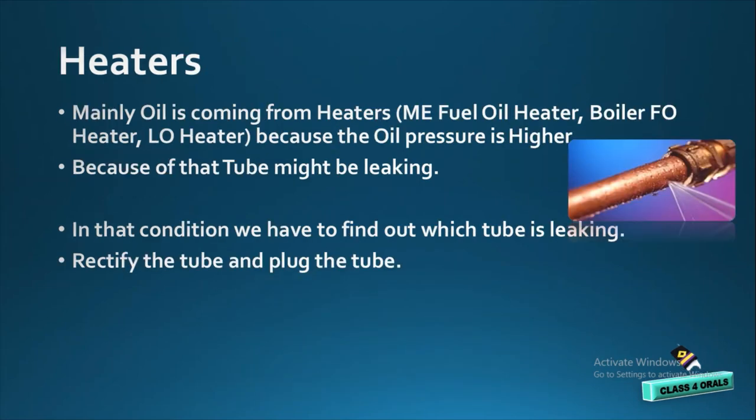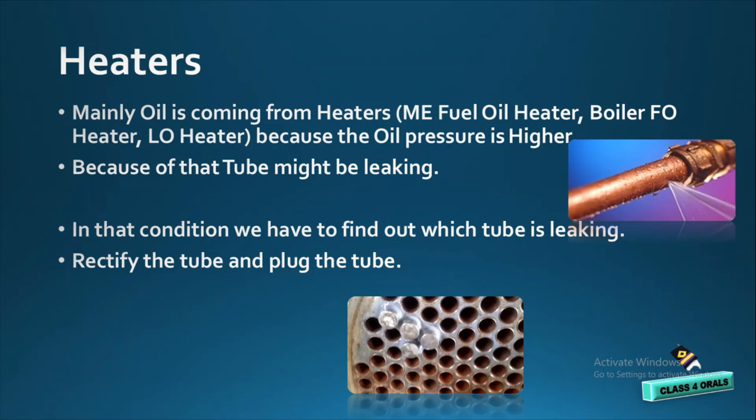Mainly, the oil is coming from the heaters — that is the main engine fuel oil heater, boiler fuel oil heater, and lube oil heater. And because of the oil pressure being higher, there can be tube leakage. In that condition, we have to find out which tube is leaking, rectify the tube, and plug the tube as shown in this figure.